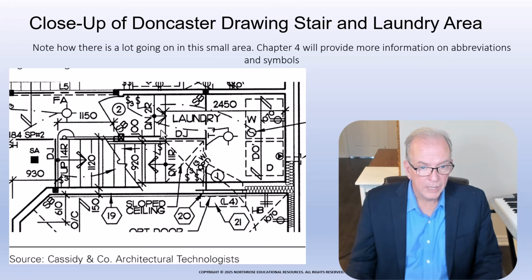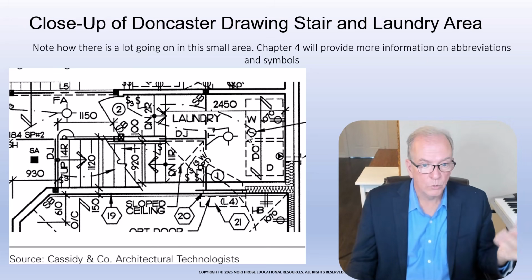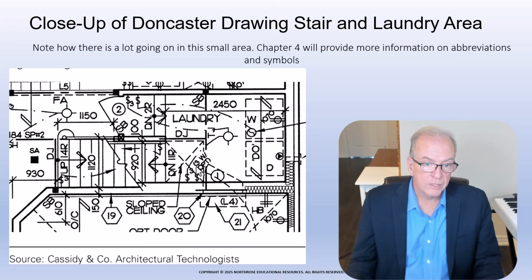I've got S3. S3 stands for three-way switch. It means I can operate the switch here and I can operate the switch there, right? A regular switch will just say S for switch, and usually has a line going through it, which is just the wire indicating where it's going to or coming from. Then it's got three-way optional. Well, if I get the door, I want to be able to turn the light on in the garage, open the garage door, walk out the front garage door and shut the light off, and then shut the door. So those kinds of things are typical in your drawings.